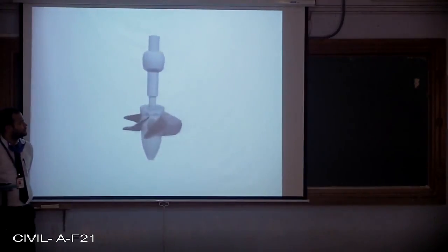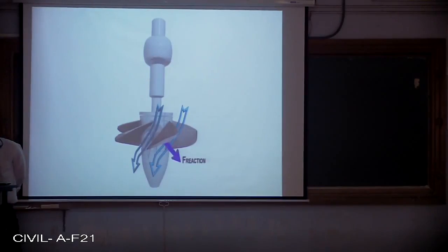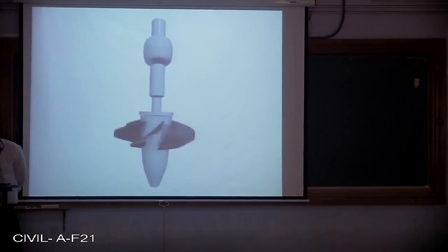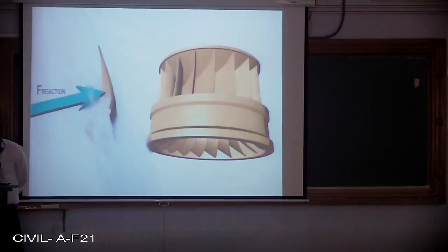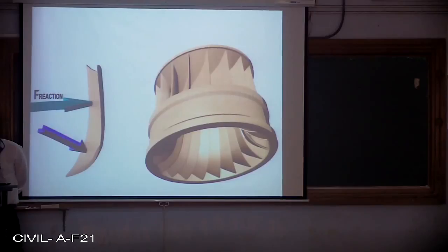Whereas Kaplan turbine is suitable for the reverse case. A high water flow will guarantee efficient production of reaction force. So when water is available at high flow rate and low head, Kaplan turbine is the best choice. Francis turbine comes in between for medium head to medium flow rate applications. Francis turbine is not a pure reaction turbine. A portion of force comes from impulse action also.